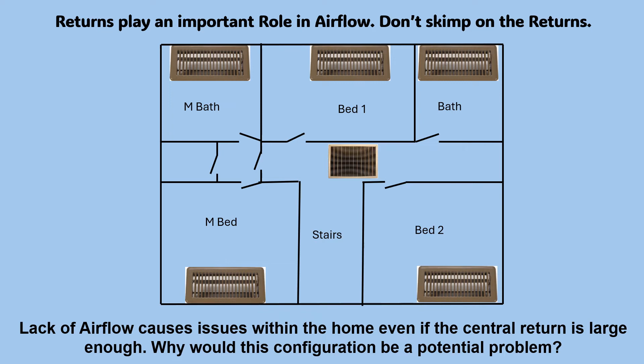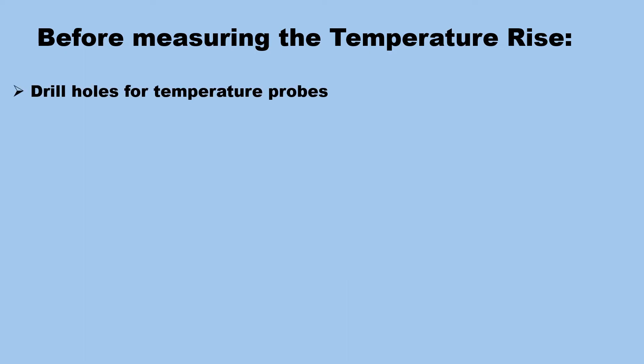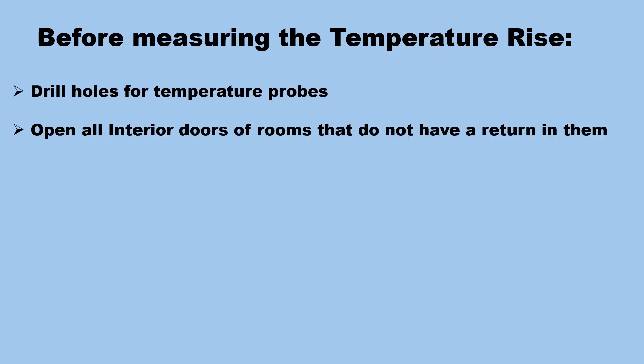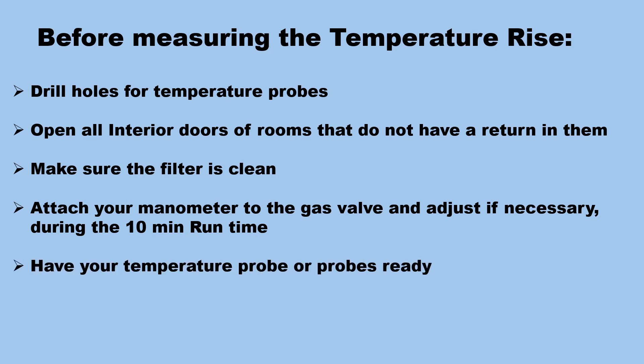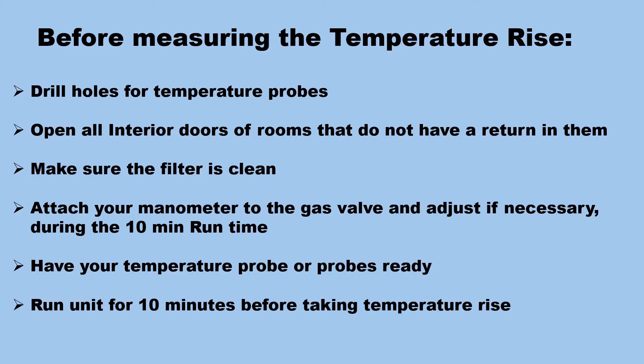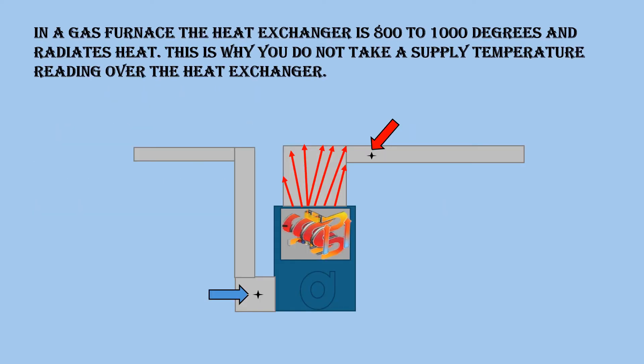And as you'll see here in a minute, it even tells you in the process of doing a temp rise to make sure that all doors are open. Before measuring the temperature rise, drill holes for temperature probes. Open all interior doors of rooms that do not have a return in them. Make sure the filter is clean. Attach your manometer to the gas valve and adjust if necessary during the 10-minute runtime. Have your temperature probe or probes ready. Run the unit for 10 minutes before taking the temperature rise. In a gas furnace, the heat exchanger is 800 to 1,000 degrees and radiates heat — this is why you do not take a supply temperature reading over the heat exchanger.